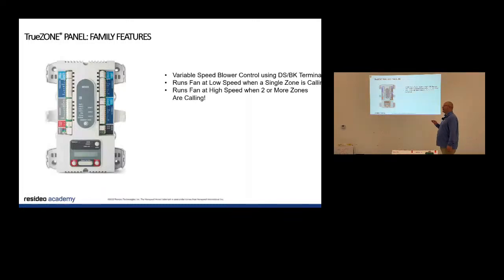But my point is, if you have 2-stage equipment, we all know that most of the time it's going to run on low stage. If I have an air conditioner that's multi-stage, I need a low stage speed for the furnace. And when there's a call for second stage, my furnace has to ramp up. All of that is done through the panel and it's compatible with any variable speed product. That's the main thing to know. Questions on that? If it's single stage, we're fine. If it's 2-stage, you just select a 2-stage panel.